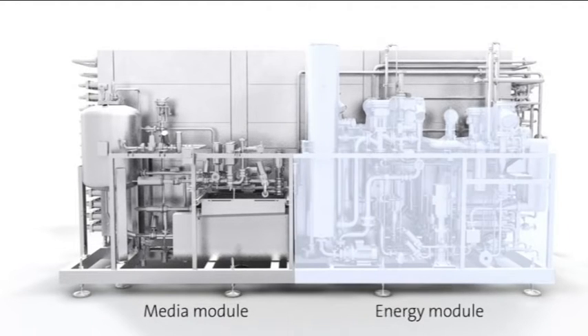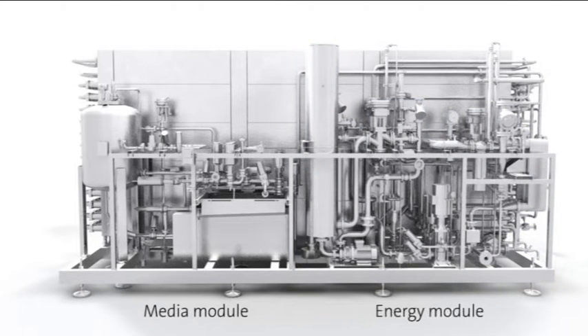On the right is the energy module which controls the supply of heating medium to the tubes. In this case, steam is converted into hot water for ultra-gentle heating of the product concerned. The cooling media, like glycol or ice water for the final cooler, are also connected to the energy module here.